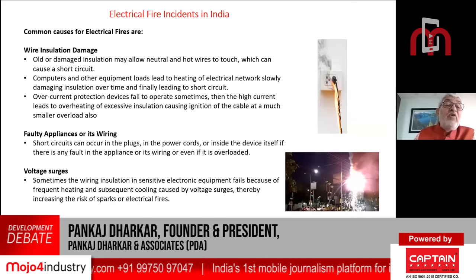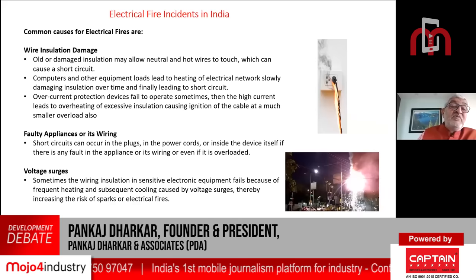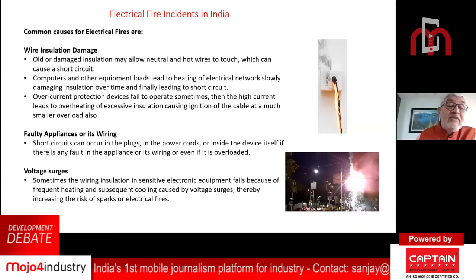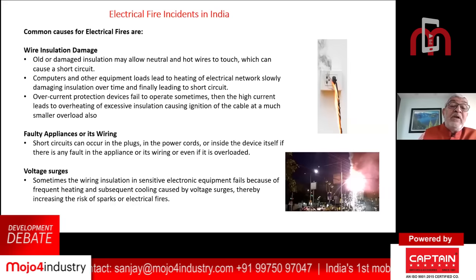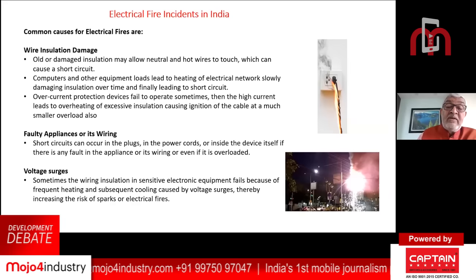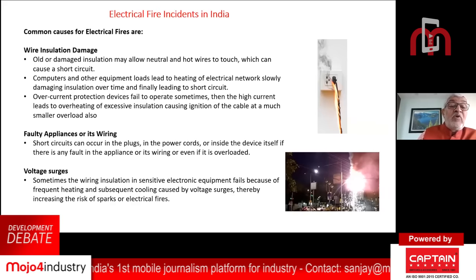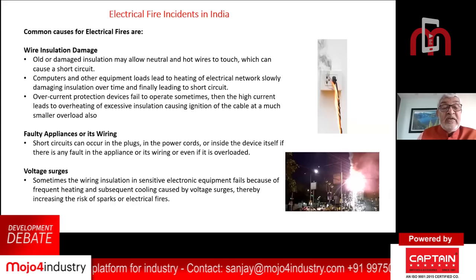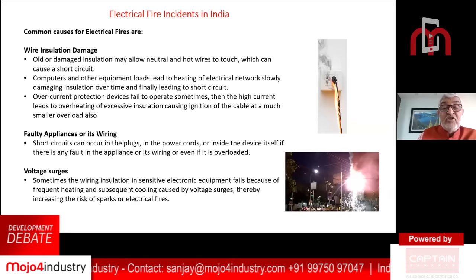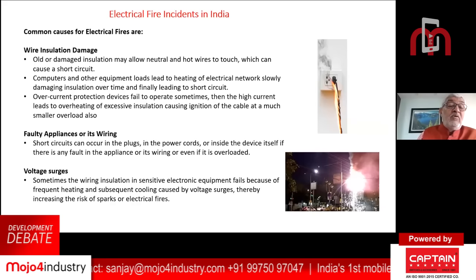If you try to analyze it, wire insulation damage is one of the major causes. Old or damaged insulation may allow neutral and hot wires to touch, causing short circuits. Computer and other equipment loads lead to heating of electrical networks slowly, damaging the insulation over time and finally leading to short circuit. Overcurrent protection devices sometimes fail to operate, and the high current leads to overheating of insulation, causing ignition of cable at much smaller overloads.